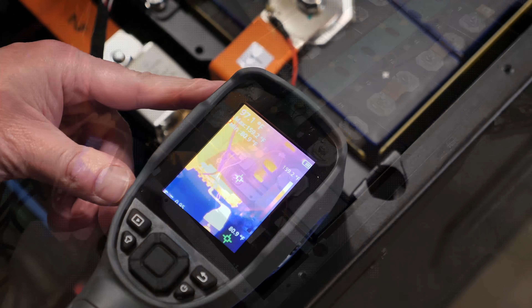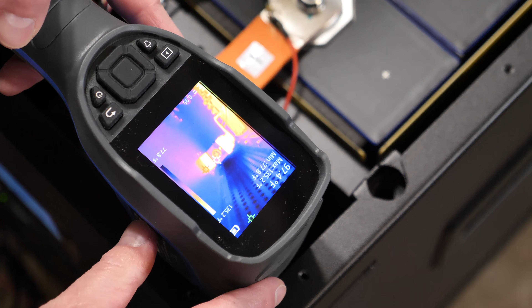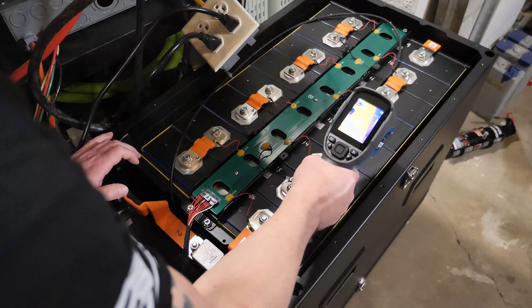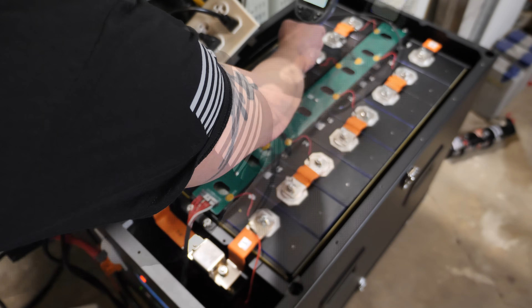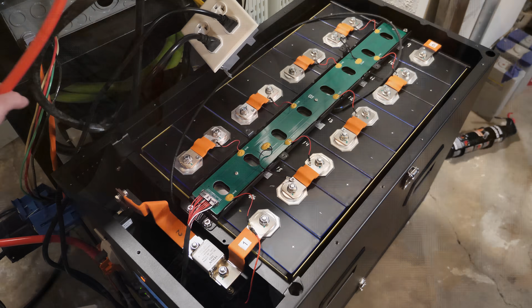I'm gonna peek over to the breaker, that's showing 120, basically right in the center. You wanna see this bus bar by this terminal, 170 degrees Fahrenheit. And if we try to peek down below to that bus bar, we're doing around 130 degrees Fahrenheit. If I go back just a little bit further to the terminal, at least the plastic part, 132 degrees. So not too bad. I do feel heat coming off of here, but it's not too bad. Yeah, 99, 98, 95 in the back. So it's just warmer up here in the front due to all the bus bars and stuff right up here. And I can still grab onto the battery cables as well.